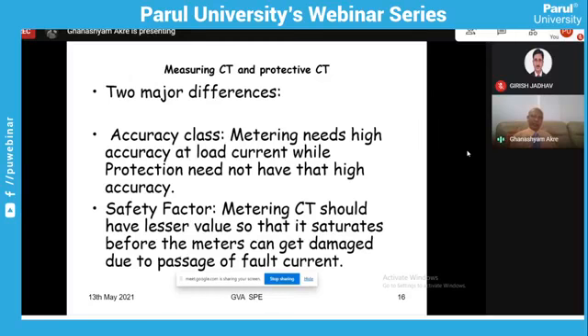In safety, the safety factor in the metering CT should have a lesser value so that it saturates before the meter can get damaged due to the passage of fault current. I have told you that when fault current flows, the primary will carry that fault current. It will not be restricted. But the secondary in the protection class should faithfully produce the secondary reflected current. That means if it is 20 times, then the secondary, in place of 1 ampere, should carry 20 amperes, so that the relays and the relay system will understand fast the severity of the fault and they will act fast or slow.